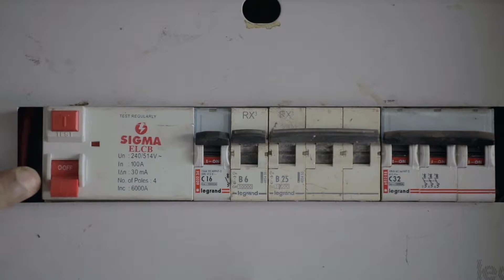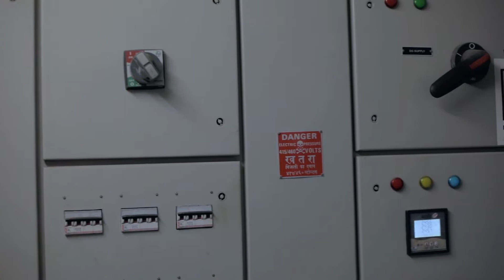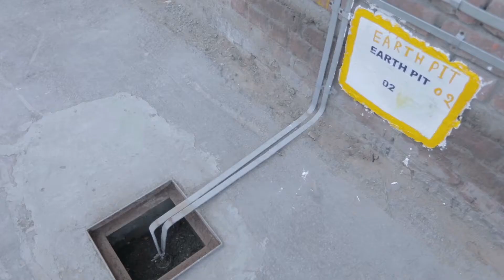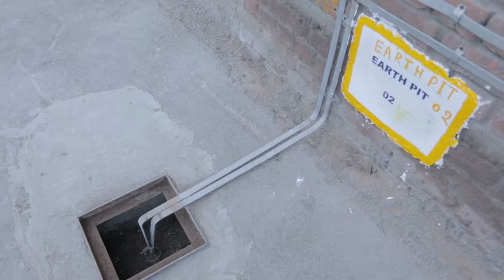Workshops must install residual current circuit breaker (RCCB) of 30 milliampere capacity on all the electrical equipments used in the workshop. All the electrical equipment should be connected to properly constructed and maintained earth pits. Earth pits should be tested for resistance and continuity at a frequency of 6 months by a government authorized electrical contractor, and the details like earth pit number, testing date and next due date should be posted on or near the earth pit.